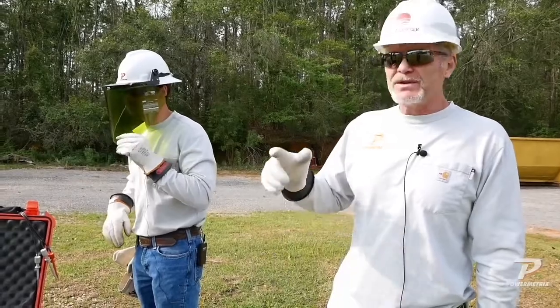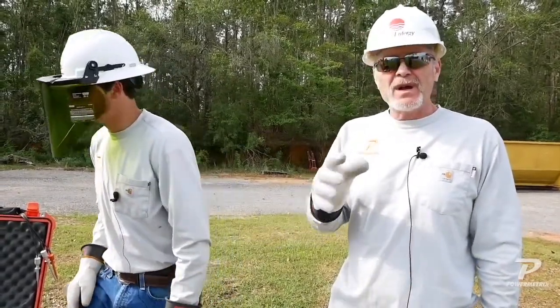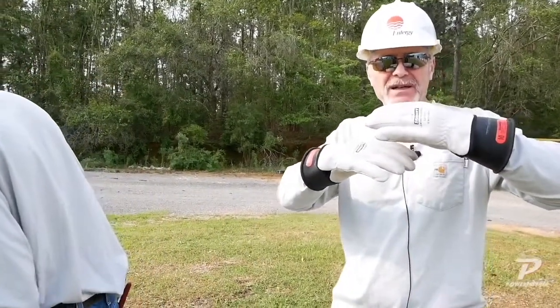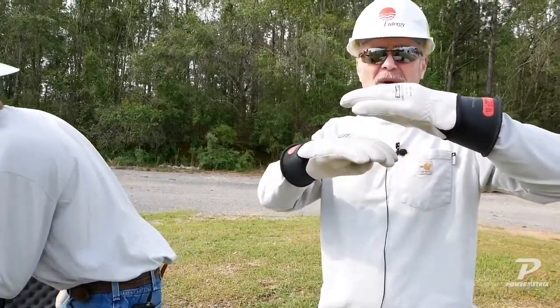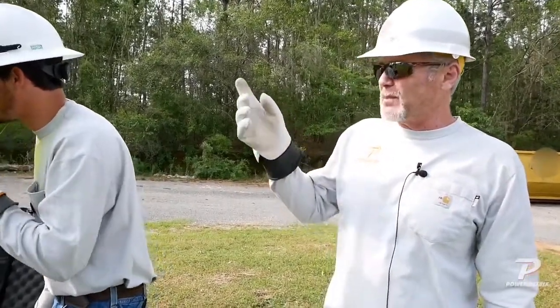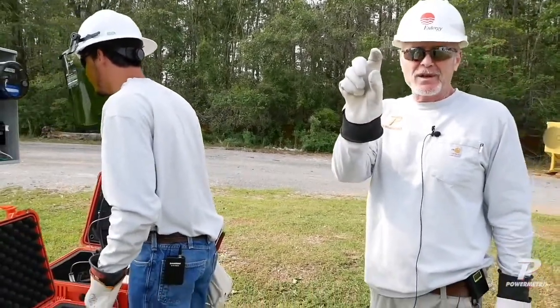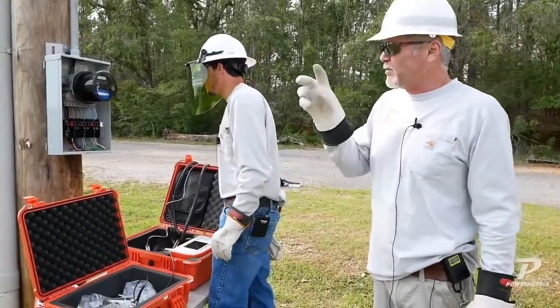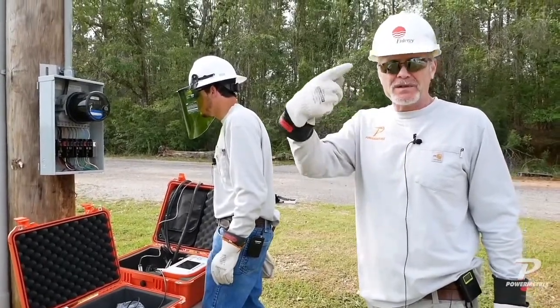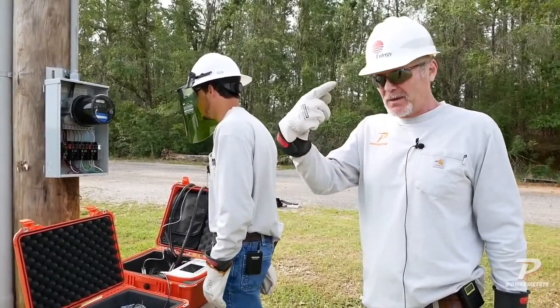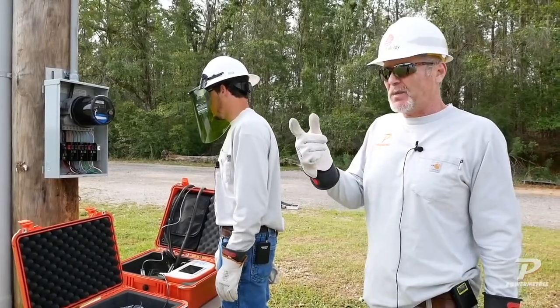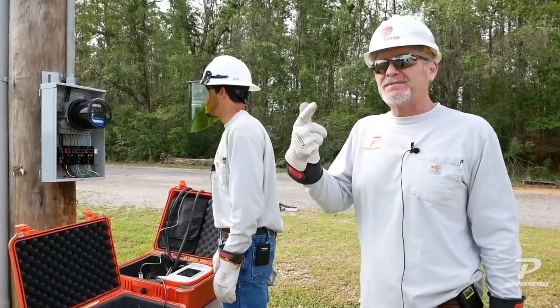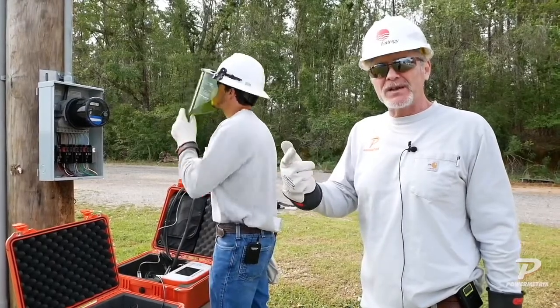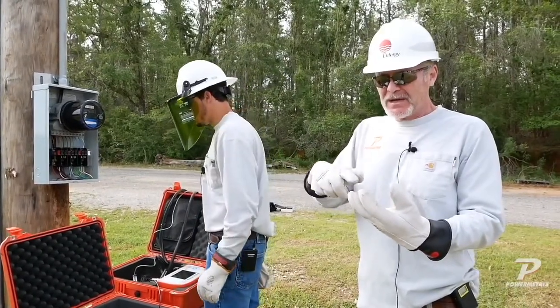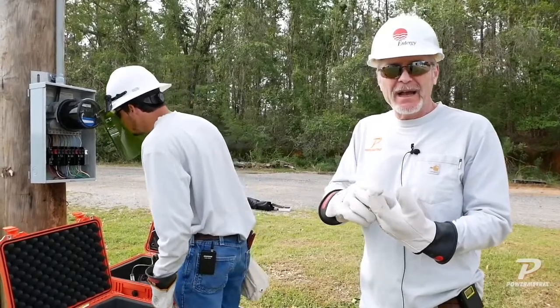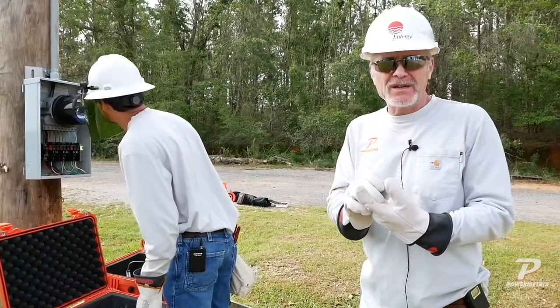So when you're doing your tests with the equipment, remember when it's doing like a customer load test, it'll say, okay, I've got pulses expected versus pulses actual. The pulses actual are picked up off of the pickup that Brylan's going to put on there on the hog nose or that COM port on the front of it, and it's going to count the pulses. 1, 2, 3. Those are the pulses actual. And then pulses expected is where we take voltage times current times power factor, we come up with watts, right? And then for this meter, you divide by 1.8, and it tells you how many pulses you should have had.